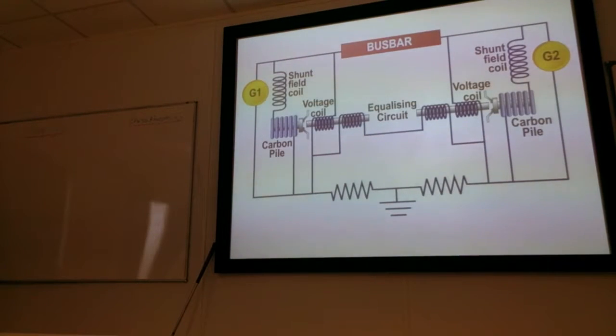If we've got two generators and we want them both to feed a common bus bar, in a process called paralleling, parallel generators must be balanced to share the same bus bar. Otherwise, if you had this one putting out 28 volts and this one putting out 27, then that would try and drive that one back as a motor. The voltage output must be matched.